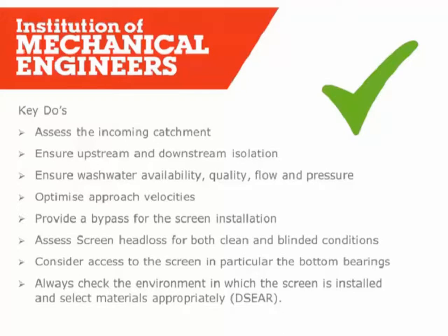Now I'm going to cover some key do's and don'ts in inlet screen installation and systems design. Apologies in advance if there's any repetition - if we say things more than once it's probably an important design consideration. First and foremost, assessing the incoming catchment: catchment can be flashy - more or less prone to the effects of sudden rainfall - or might involve open culverts or other sources of non-domestic sewage. Knowing your catchment will help you determine if a coarse screen is a sensible investment and help determine your expected peak screenings loading. High peak loading can be accommodated hydraulically through greater freeboard in your inlet channels or by providing assist screens that operate when the last duty screen is overloaded. Knowing your peak load also helps you to size the screenings handling plant downstream.